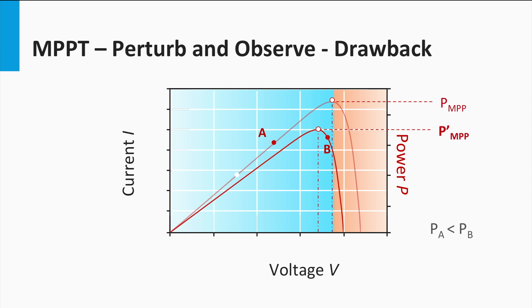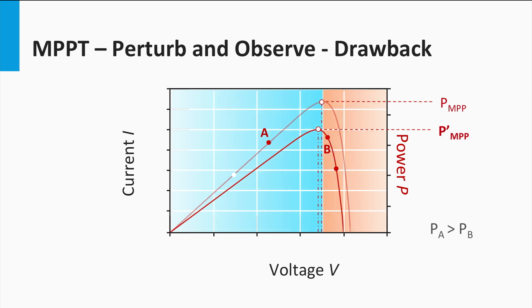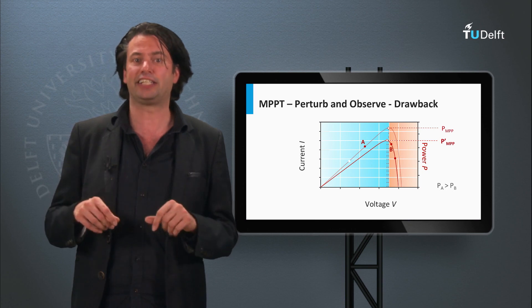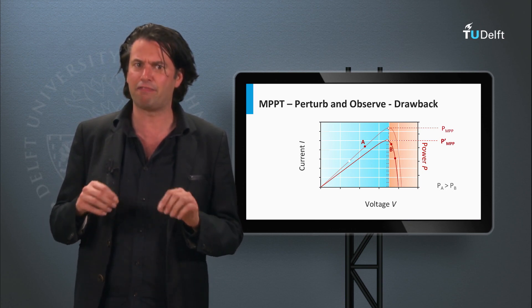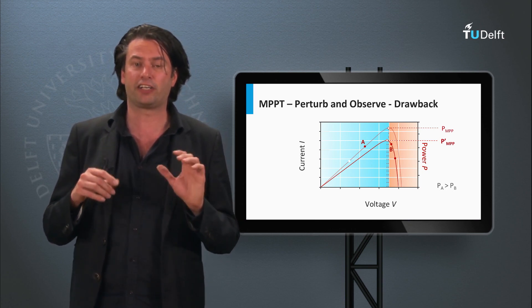But the MPP still lies to the left of point B, which makes the algorithm think that the MPP is to the right of point B. This is detrimental to the speed of convergence of the P&O algorithm, which is one of the critical figures of merit in MPP tracking. Thus drastic changes in weather conditions severely affect the algorithm's efficacy.